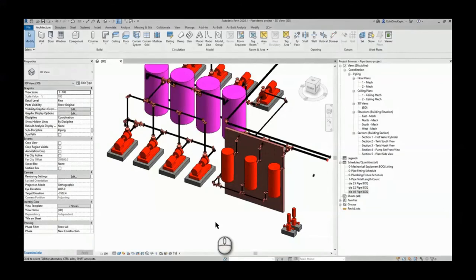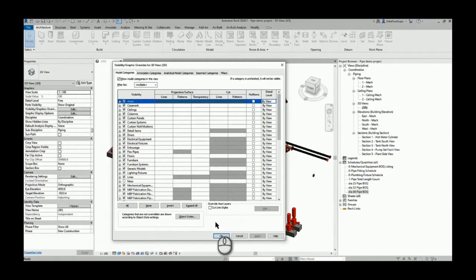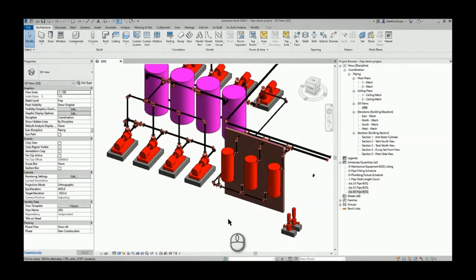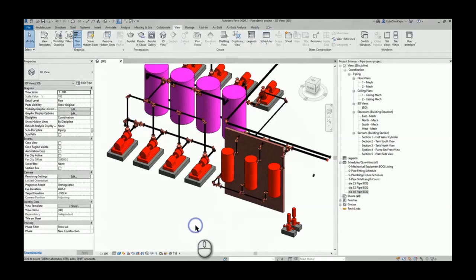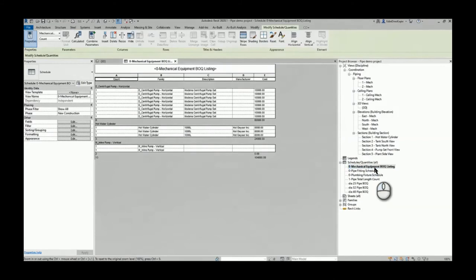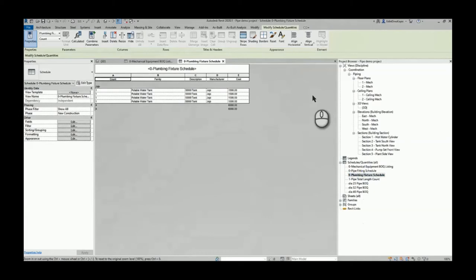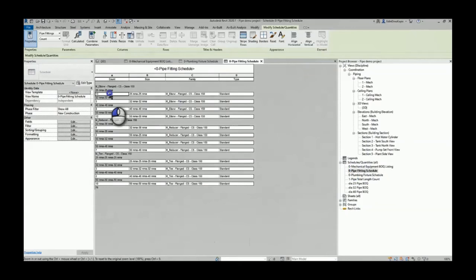Let's take a look at this within the Revit environment. In Revit, everything has its place. All pipes, all equipment, all fixtures are registered under their own category within the Revit space. Because of this filing capability and the parameters attached to our elements, everything within the Revit project can be quantified. In the View tab, within the Schedules box, you can drop down and create your own types of schedules and quantities. In my project, I've got a schedule for mechanical equipment listings and BOQ with cost parameters attached to it. The same for my plumbing fixtures and tanks. If I navigate to my pipe fittings, I can isolate every single pipe fitting size within my Revit project.